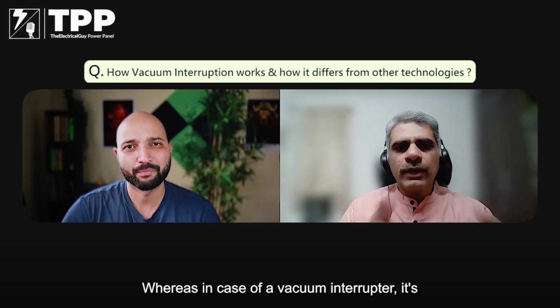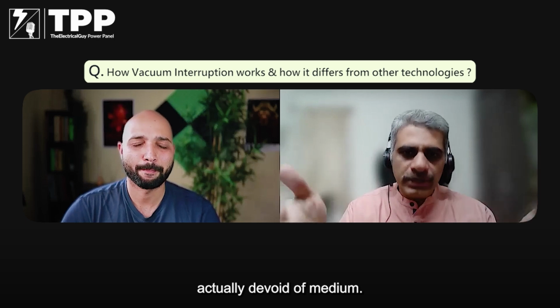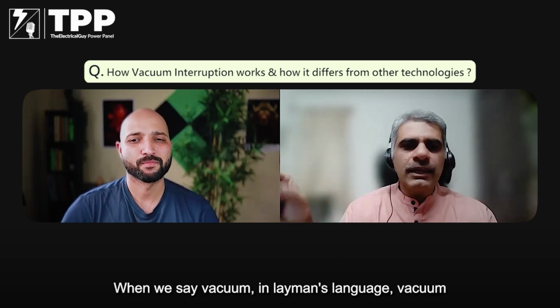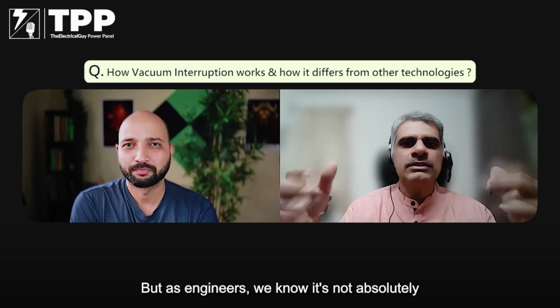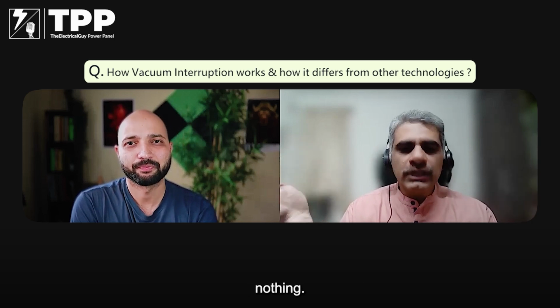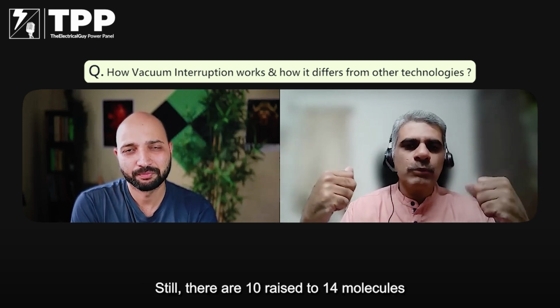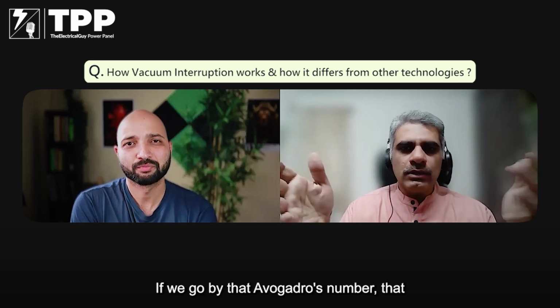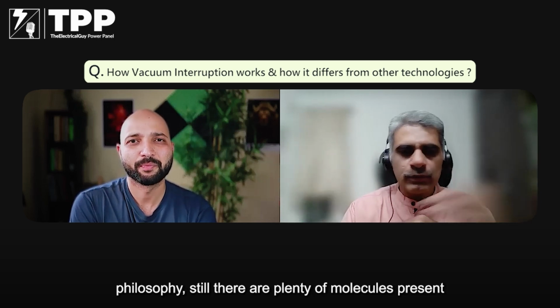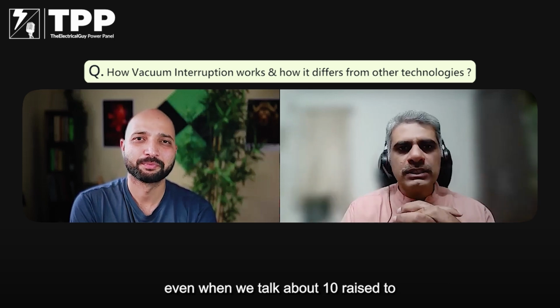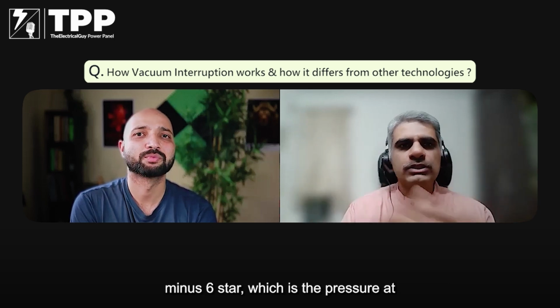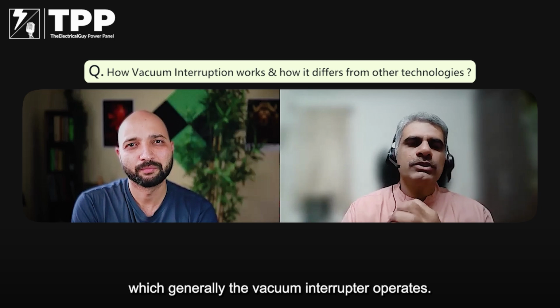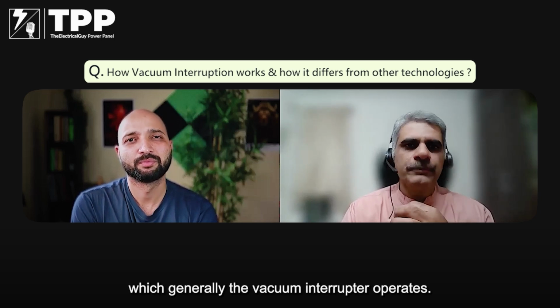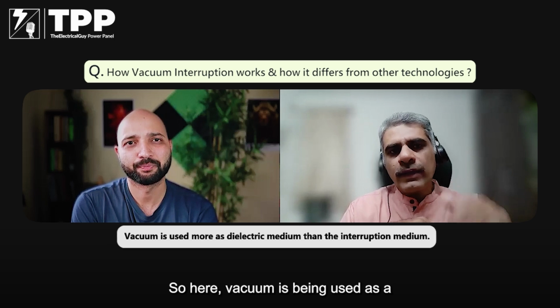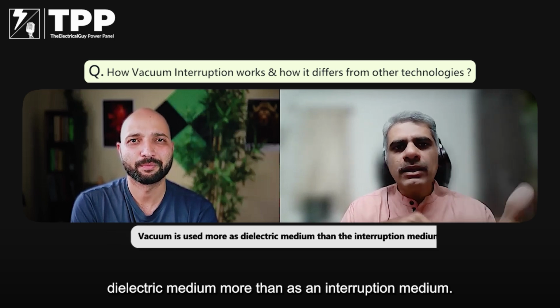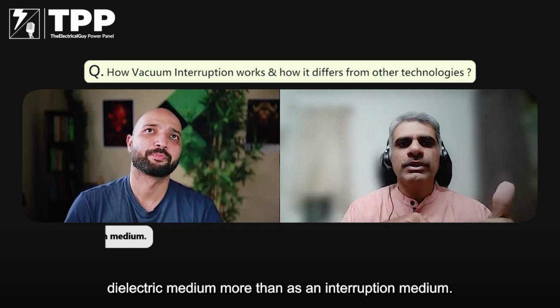Whereas in the case of a vacuum interrupter, it's actually devoid of medium. When we say vacuum, in layman's language, vacuum means nothing. But as engineers, we know it's not absolutely nothing. Still, there are 10 raised to 14 molecules per cm square. If we go by Avogadro's number, there are still plenty of molecules present, even at 10 raised to minus 6 torr, which is the pressure at which the vacuum interrupter generally operates. So here, vacuum is being used as a dielectric medium more than as an interruption medium.